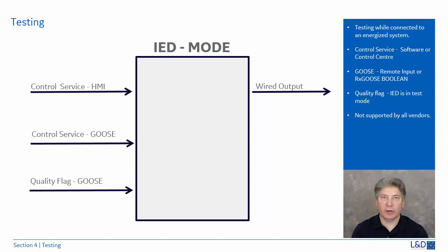Let's review the different configurations available. First, we'll take a look at the mode where it's set to off. The test bit is set to false. The Q.test is equal to false. The logical node is disabled, and we have no output control.